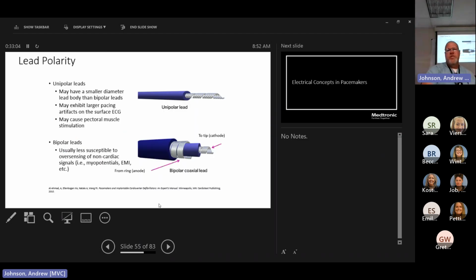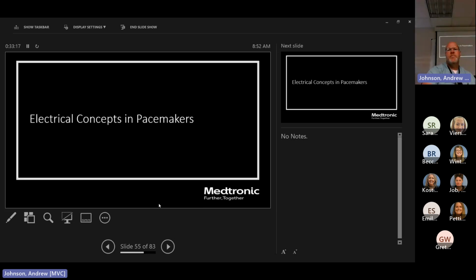This shows the filaments on the inside, the unipolar lead and the bipolar lead, and you can see the insulation between that cathode and anode on the bottom lead there.